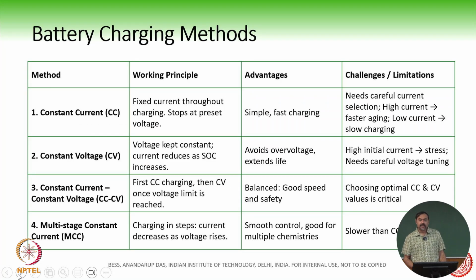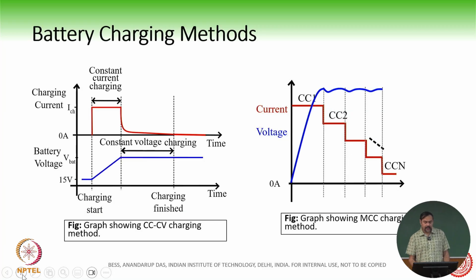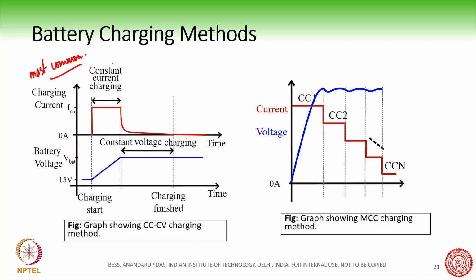You can see this through the curve. This is the most common way of charging a battery. Initially you charge the battery at a constant current level, so the battery voltage rises. After the battery reaches a certain value, typically 90% of the rated voltage of the battery, then you shift to constant voltage charging.